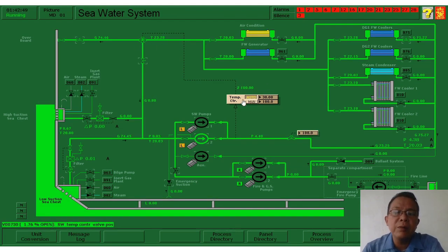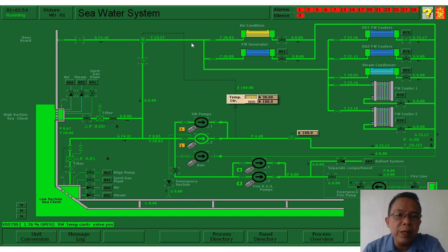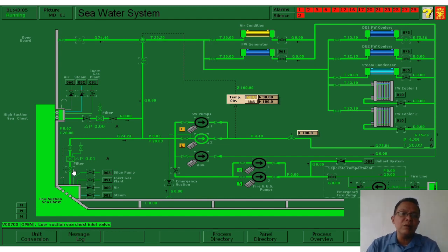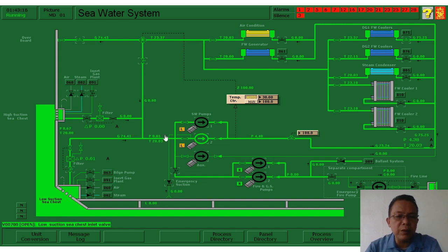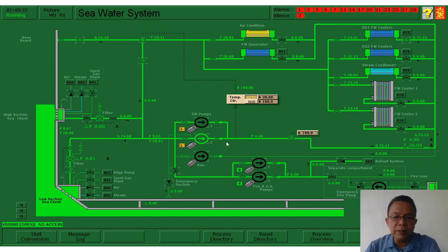The controller adjusts the three-way valve and also adjusts the suction. When we are closing the overboard, we let the discharge recirculate back to suction — we don't need sea suction from outside. We do not close it totally because the temperature would rise abruptly. So slowly, the controller takes charge of the temperature in the system.